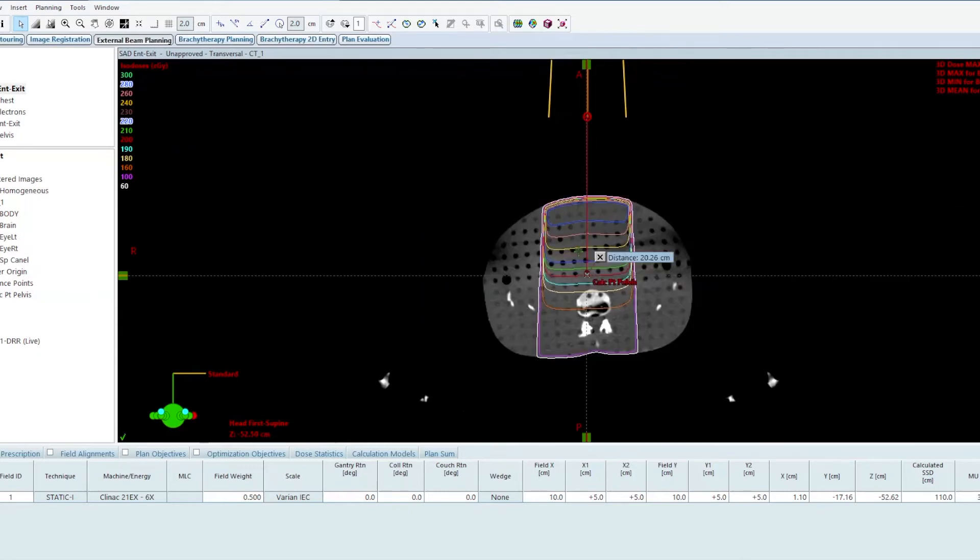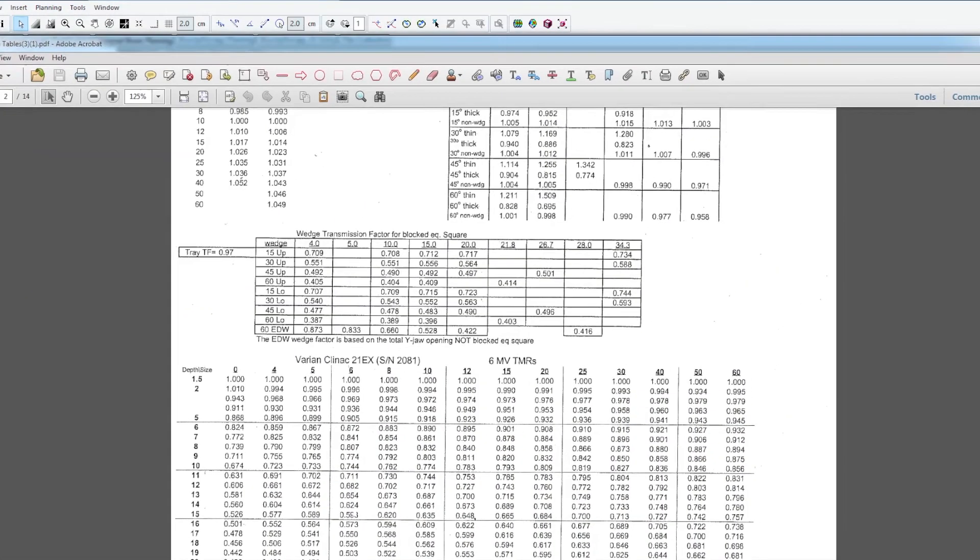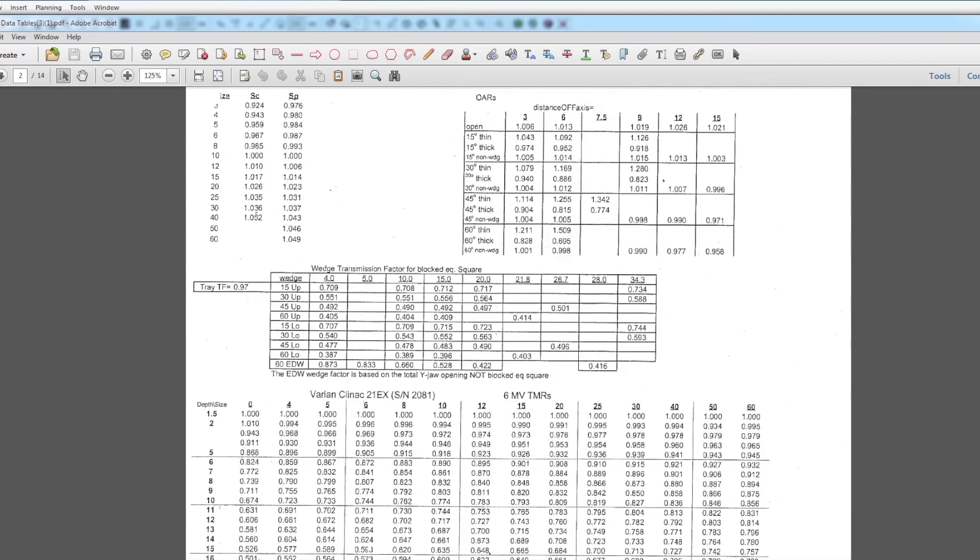If I pull down my data table for 6x and I look at 12 centimeters, collimator scatter factor is 1.01, phantom scatter factor 1.006.